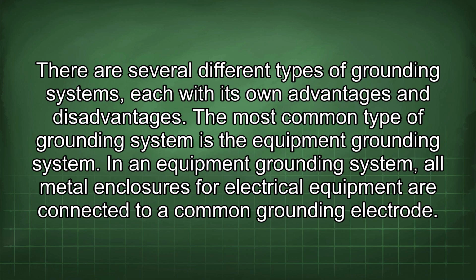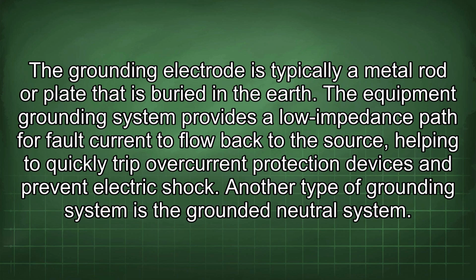The most common type of grounding system is the equipment grounding system. In an equipment grounding system, all metal enclosures for electrical equipment are connected to a common grounding electrode. The grounding electrode is typically a metal rod or plate that is buried in the earth. The equipment grounding system provides a low impedance path for fault current to flow back to the source, helping to quickly trip overcurrent protection devices and prevent electric shock.